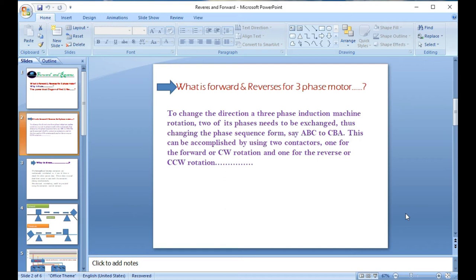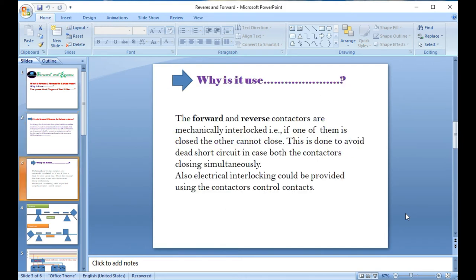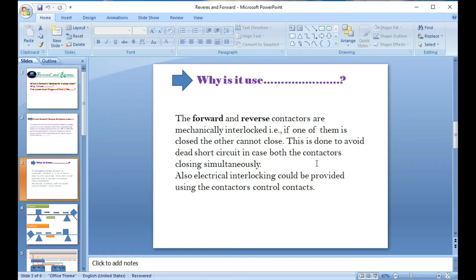Why is forward and reverse used? Basically, in a factory, forward and reverse contactors are always interlocked. Interlock means that when forward is running, you can never run reverse at the same time. This also applies to star-delta connections. If one contactor is closed — meaning forward is running — the other cannot close; it is totally off. This is done to avoid a dead short circuit caused by both contactors closing simultaneously.